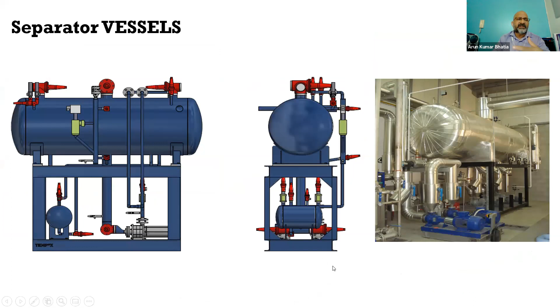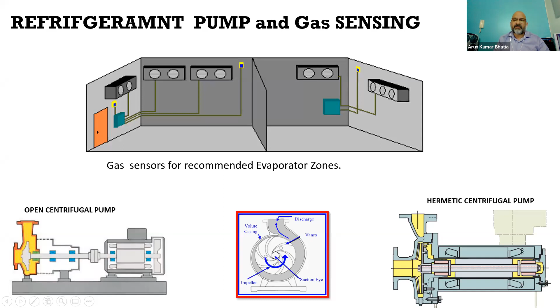Then there are other components in the plant room, like separator vessels, surge drums, or suction accumulators — these are vessels. In pumped refrigeration systems, we also have pumps, hermetically sealed or open type, used to pump refrigerant from the plant room to the desired evaporator or heat exchanger to generate the refrigeration effect. You may have heard of low charge refrigeration systems — pumps play an important role there. That's an entirely different topic; we may discuss it another day.